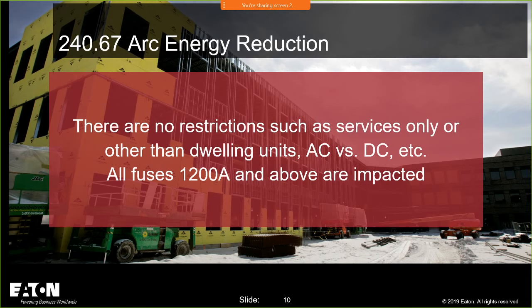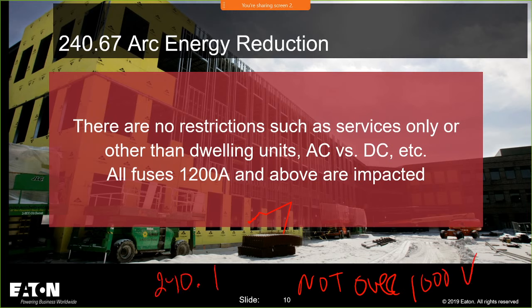So what I do have to add to this slide, I'm going to make a note. I'm going to say not over 1,000 volts. 240.1 is your reference. Understand when that applies. So 240.1 tells us that that is the only restriction. So no restrictions is not quite right. I do have to fix that slide. Reference 240.1, and it only applies up to 1,000 volts.